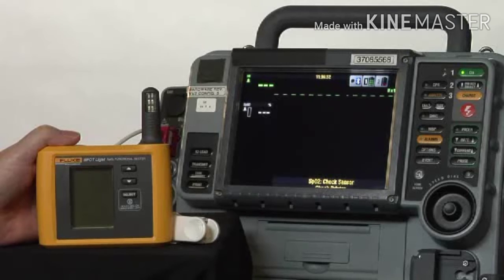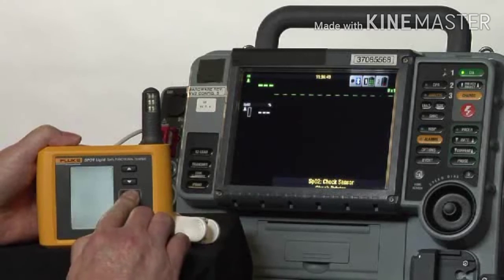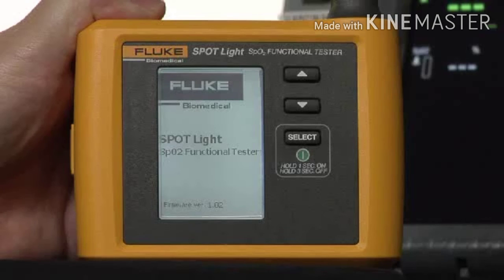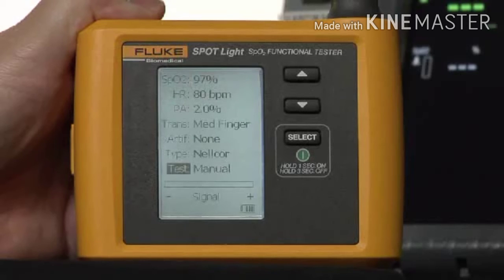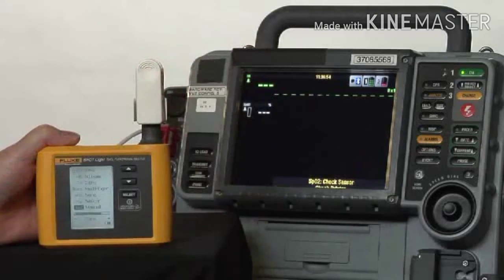In this case, we find the device turned on. It's a defibrillator, and we will turn on our Spotlight SpO2 functional tester, wait for it to go through its self-check, and we will then connect the oximeter sensor from the medical device, and we'll watch this bar down at the bottom. It's called the signal strength bar, and you can see that it has a good signal, and you will begin to see the display on the screen of the defibrillator.